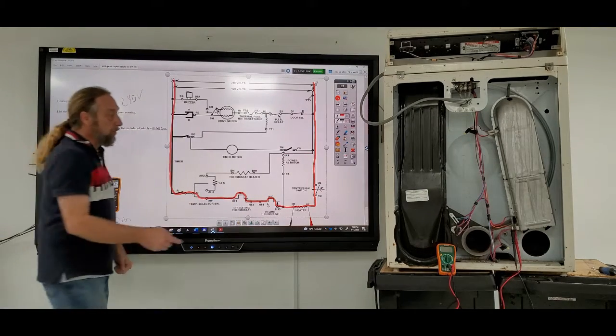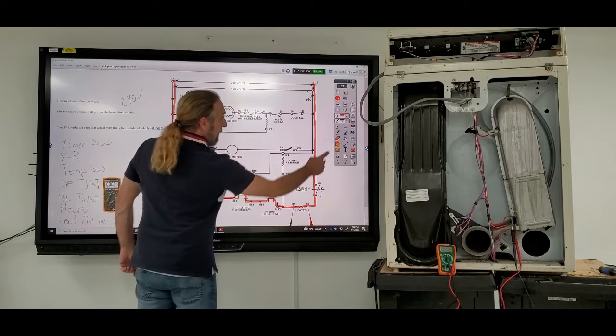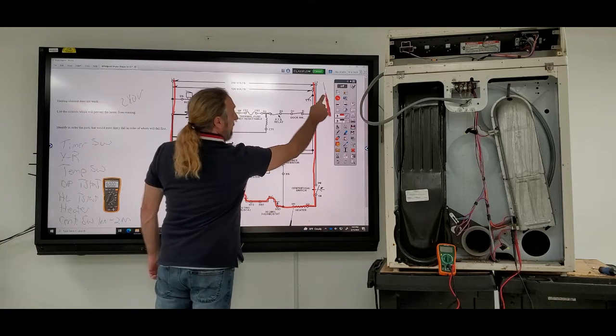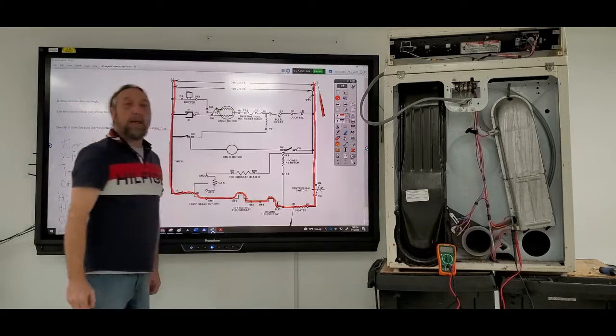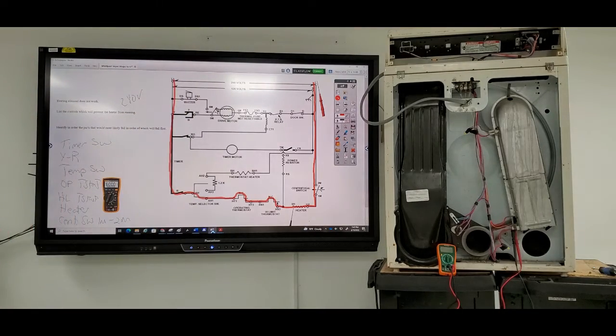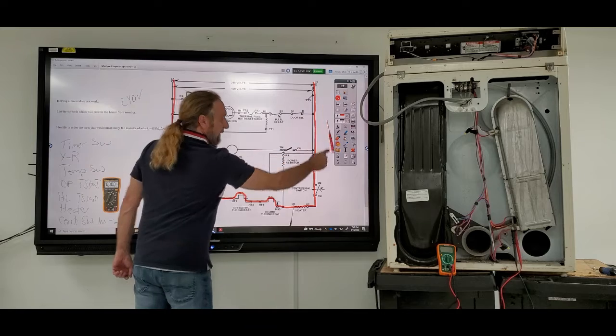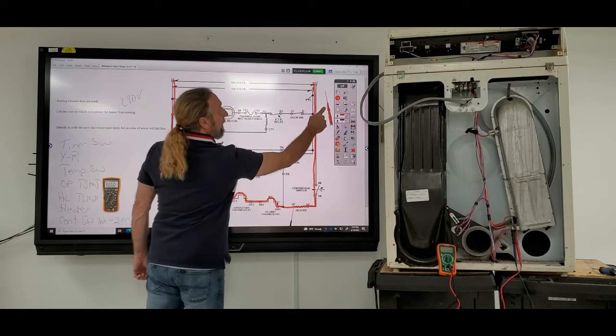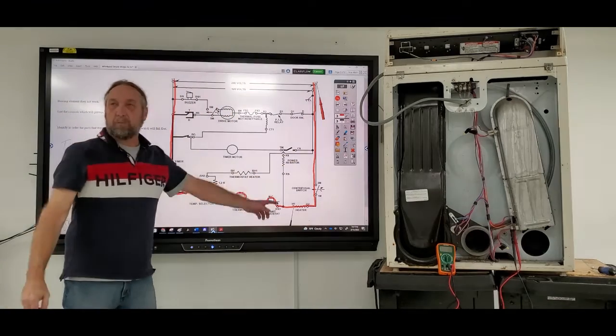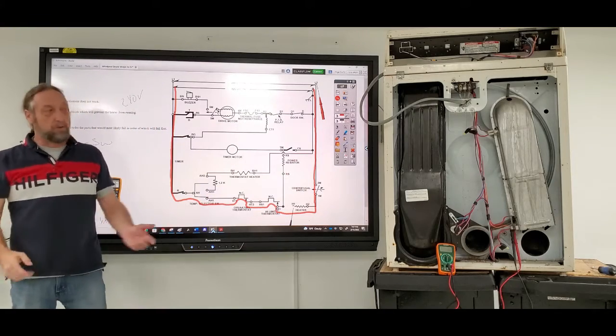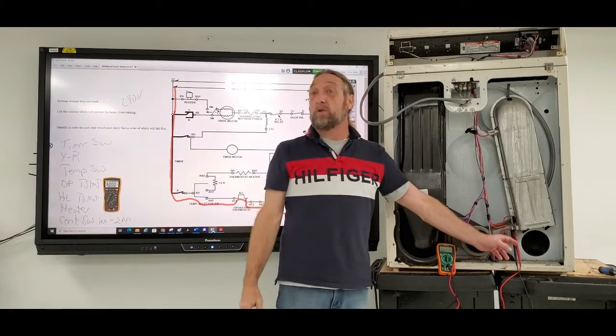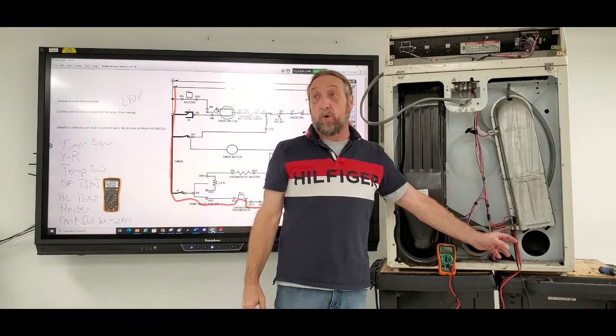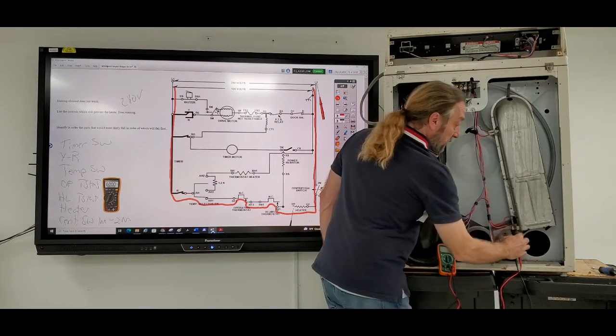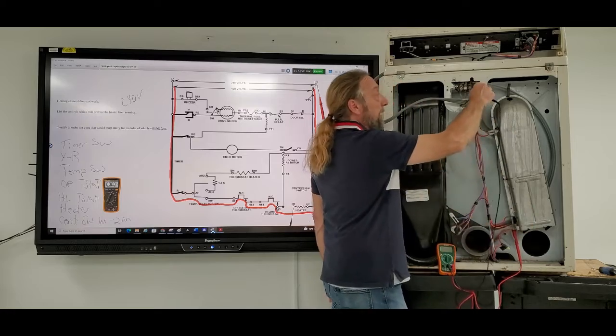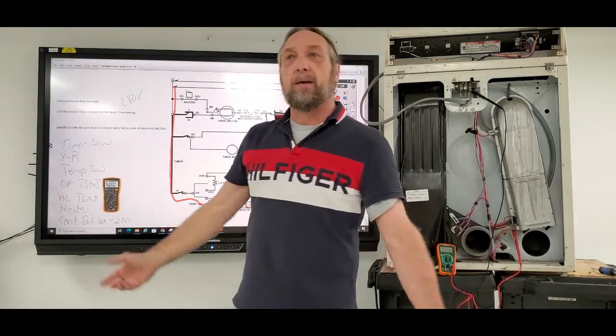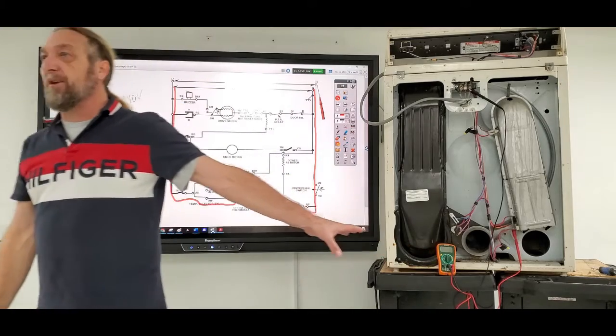So if I move one meter lead here to line 2 and leave the other meter lead there, now I got 240. I did not have it here, but I do have it here. What's between that test? The centrifugal switch. So it doesn't matter which one I take off the heater right now, I didn't have voltage. All I'm going to do is move my meter lead here, to line 2. Do I have voltage now? Yeah, I do. Okay, my problem is the centrifugal switch.